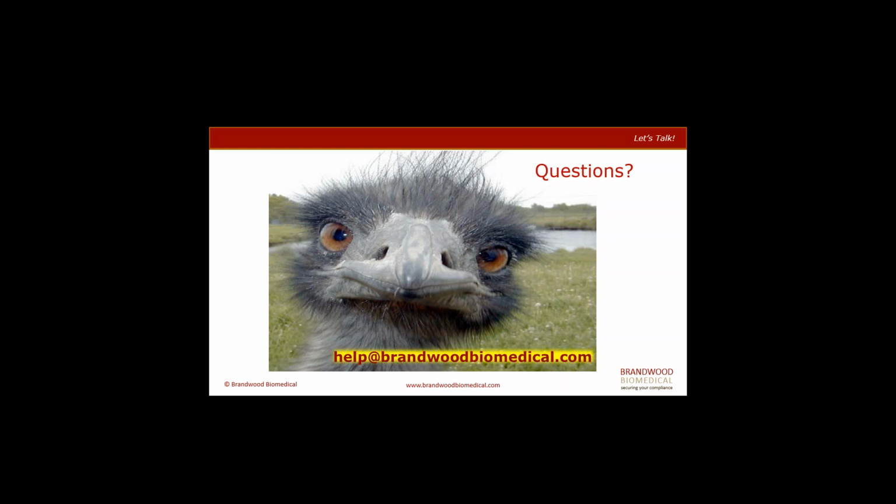more expensive process adaptations. For example, 3D printing is being more highly used now to prototype devices in a more rapid sense over technologies of days past. So yes, prototyping is considered part of design control, but you will also identify what is the relevant aspects of the prototyping you're undertaking, and in what part of that process it is involved in.